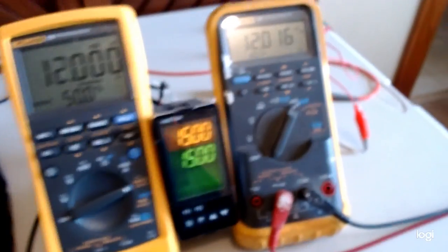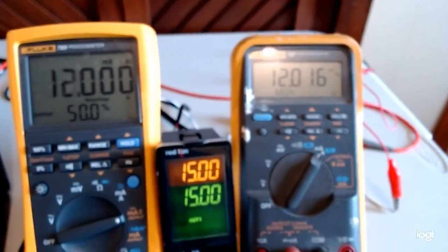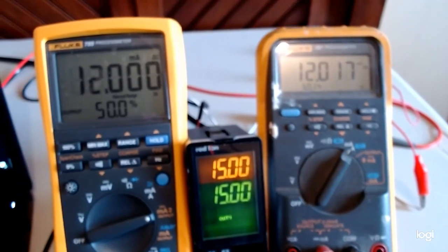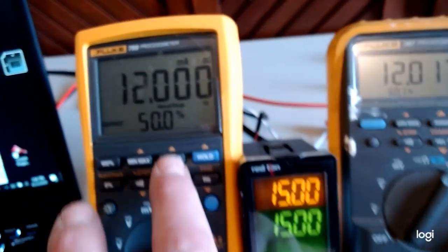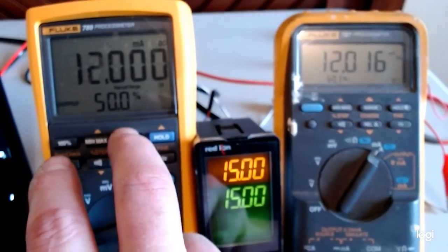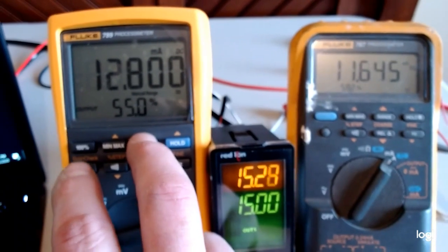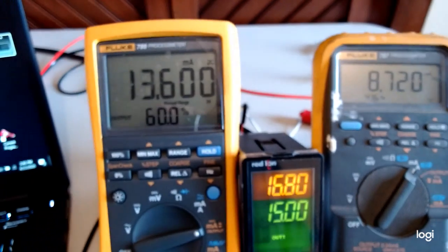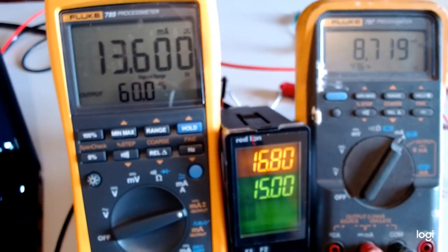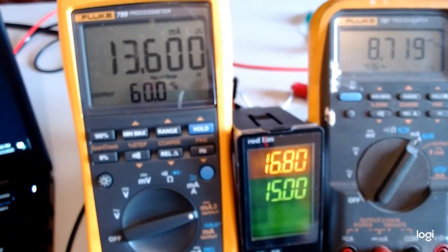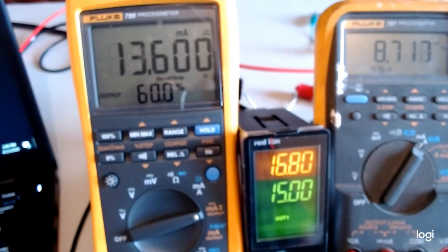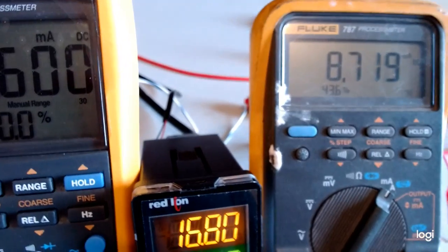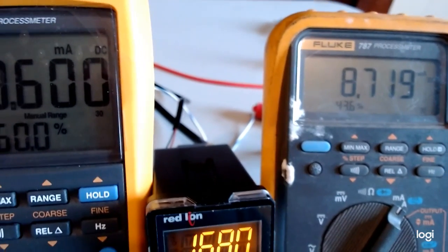So we're going to come over to the controller, and it's still sitting here. Nothing's changed because we don't have any error. As soon as we have error now, we would anticipate that we're going to get twice as much change in output. So I'm going to go up by 10%. I'm going to go up to 13.6. And what we would expect to see on the output is a 20% change, okay? Well, 20% of 4 to 20 milliamp would be 3.2. So from 12 milliamps, we should have come down to 8.8, okay?